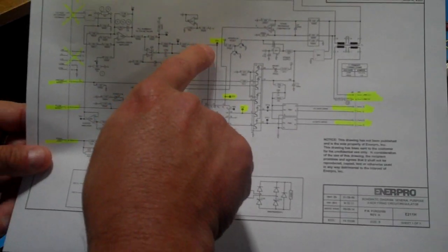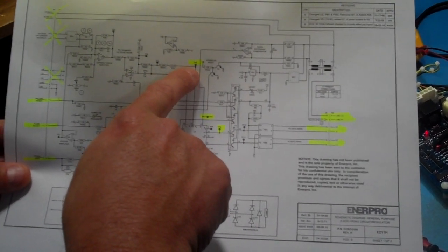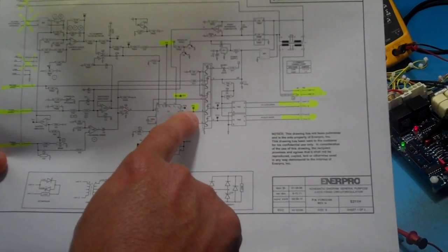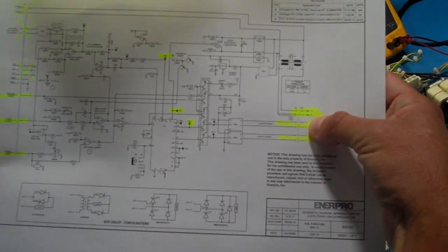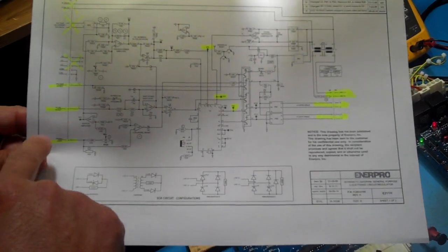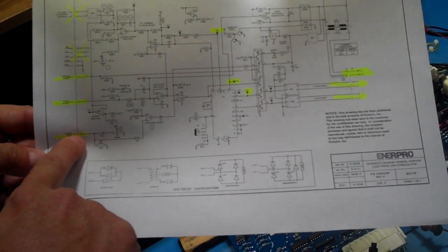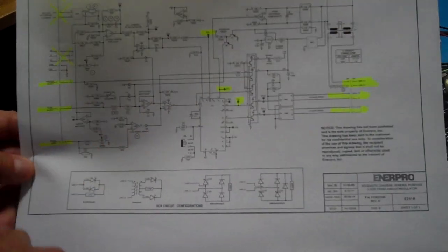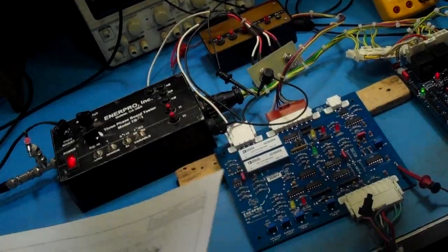The test points that we looked at were the reference, test point 7, and TP8, the delay angle, and you could measure TP9, but in this particular case we were looking at the output of the pulse modules, open circuit voltage, and we were bringing in our sig high between J1 positions 10 and 11, and of course at some point we had to enable the board. So this is the end of this first video.